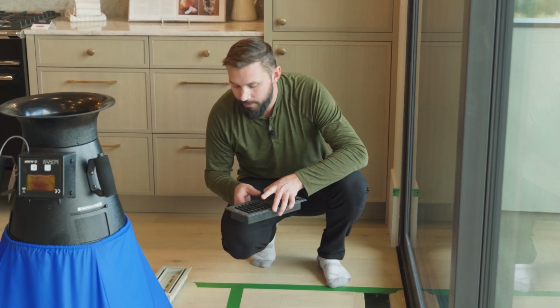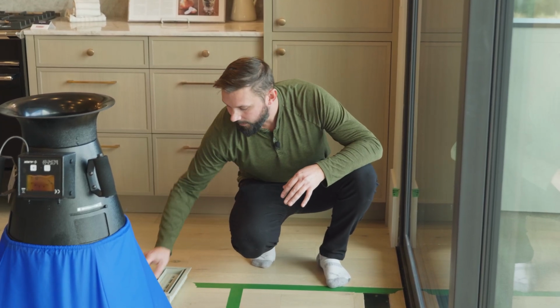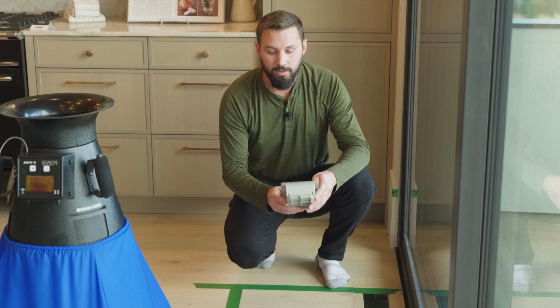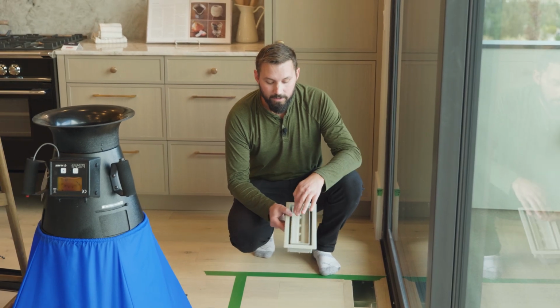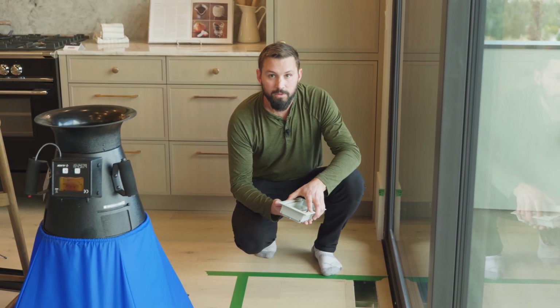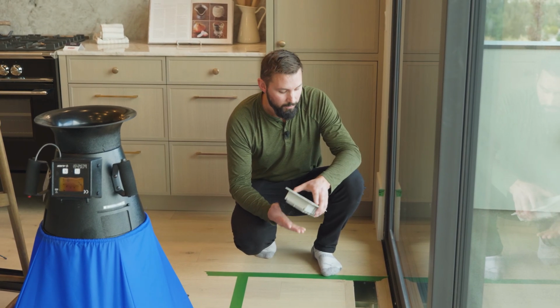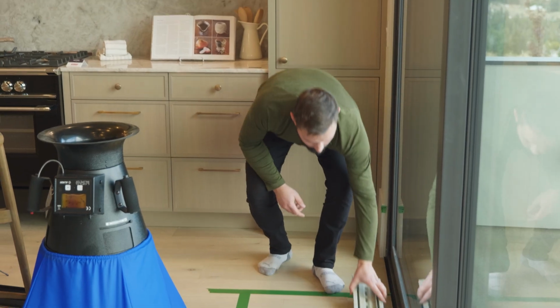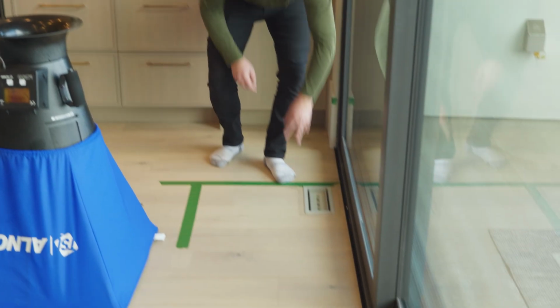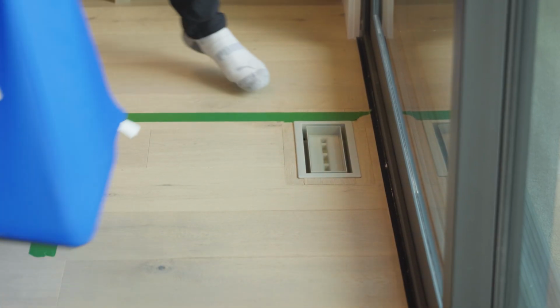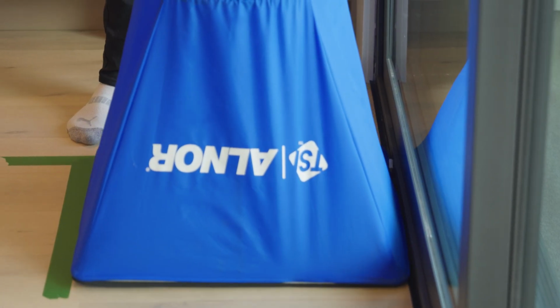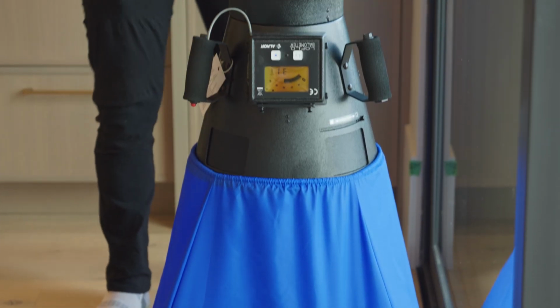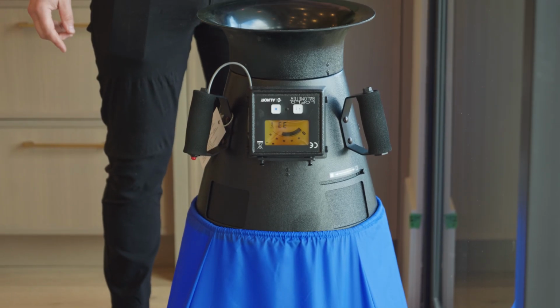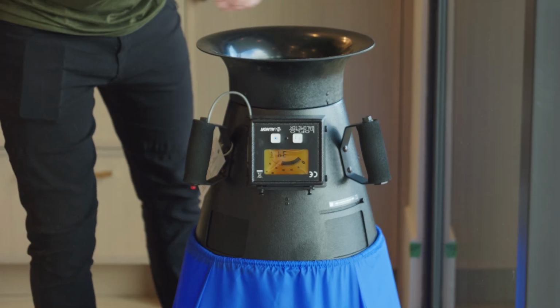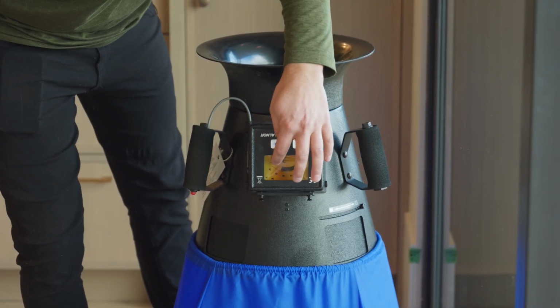If we end up with a client who all of a sudden makes a decision to use this type of flooring insert vent cover, that's going to introduce a whole lot of restriction that we weren't planning for. And you can see that with that in, compared to the baseline of what I just showed, we only get a certain amount of airflow through there. It's a restricted airflow that we have to be planning for in the very beginning. So we want to make sure that we've had those conversations with our clients.